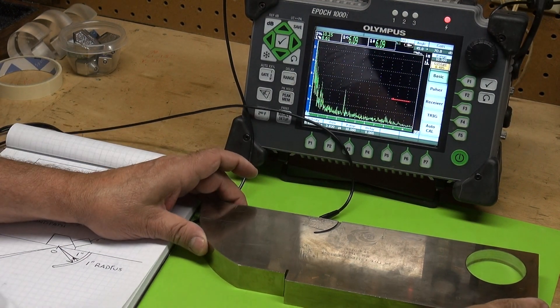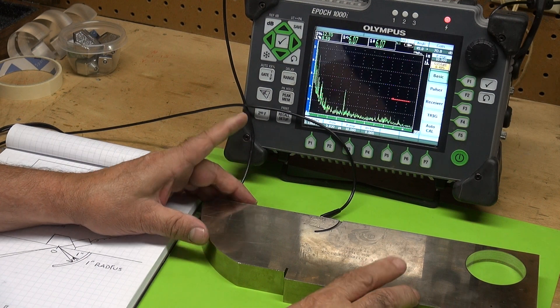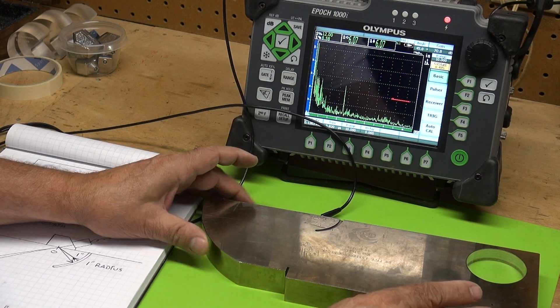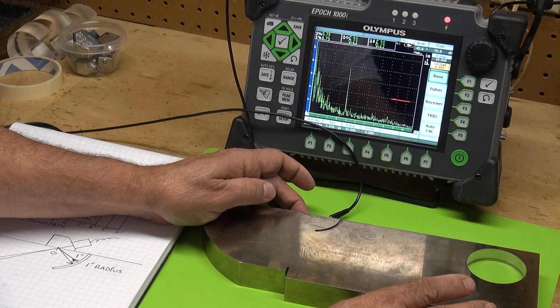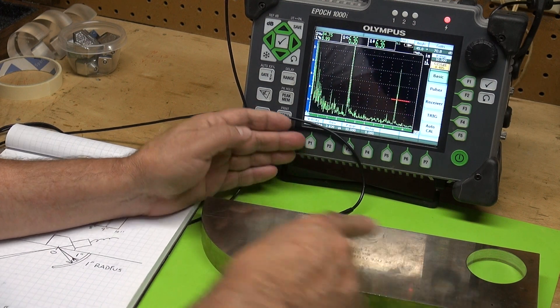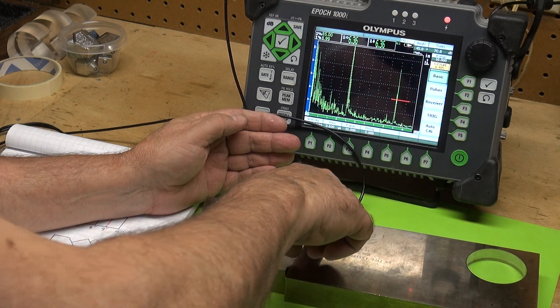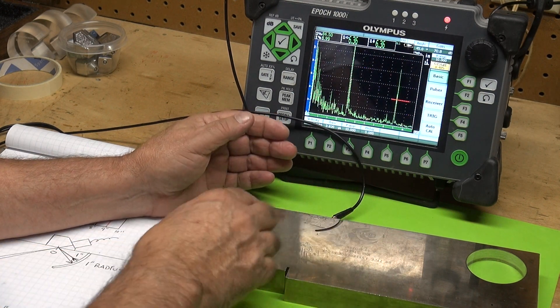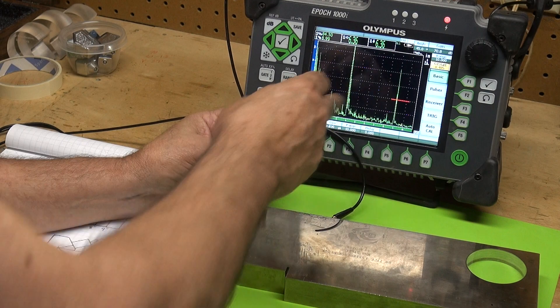I want to say a couple things about the IIW type 1 reference block. This is a block that we use to calibrate with and it has a 4 inch radius and a 1 inch radius, so we'll get a signal at 4 inches and 9 inches.